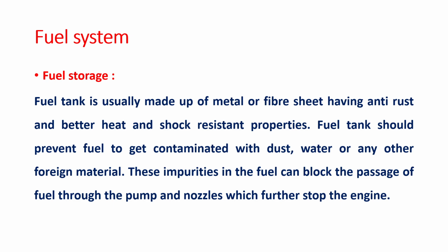As I said, fuel tank, the name implies it's a reservoir of fuel, which will be made of mild steel sheet, it's not GI. It has to have sufficient capacity to store fuel for about 10 hours. Inside the tank, 2 or 3 baffle plates will also be provided to give more rigidity and to prevent the fuel from surging from side to side.